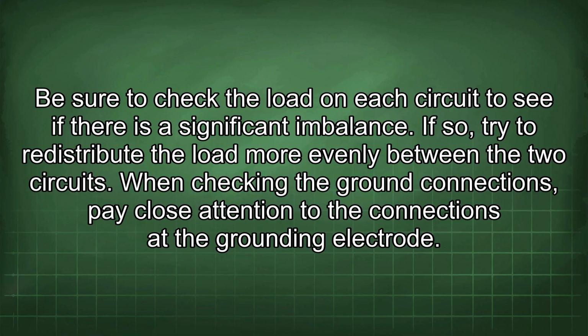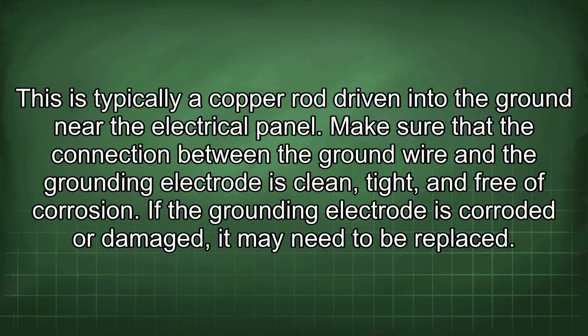When checking the ground connections, pay close attention to the connections at the grounding electrode. This is typically a copper rod driven into the ground near the electrical panel. Make sure that the connection between the ground wire and the grounding electrode is clean, tight, and free of corrosion. If the grounding electrode is corroded or damaged, it may need to be replaced.